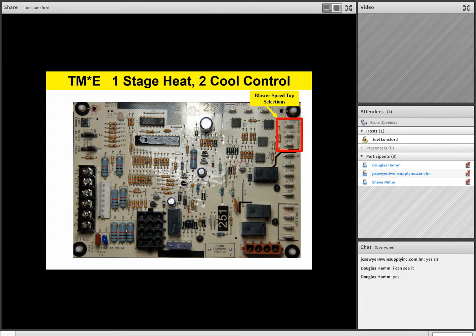To give an example, let's say we have a 2-ton unit outside, he'd want to set that high cool speed up for 800 CFM. And then his low cool would be 65% of that. And then the heating speed will be based on the size of the furnace and so on. And so the ability to change those speed taps and select high cool, low cool, and heating speed is an important setup procedure for our technicians. Any questions or comments on that?